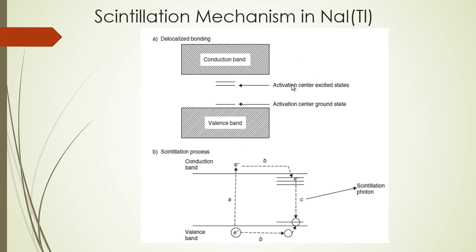This large number of photons in the UV or blue range produces the flashes of light — the scintillations — in the sodium iodide detector. Here is another diagram that illustrates the process: process A shows an electron going to the conduction band, which cannot return directly; it leaves a hole, so an electron from the activation center ground state fills the hole, and the conduction band electron drops to the activation center excited state. Process C then leads to the emission of a scintillation photon.